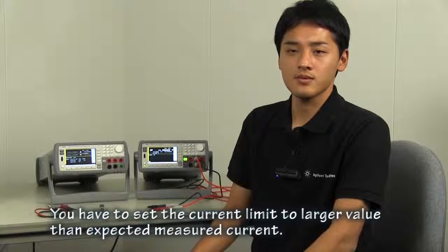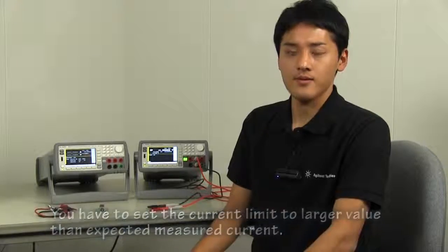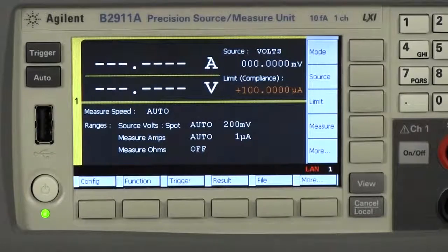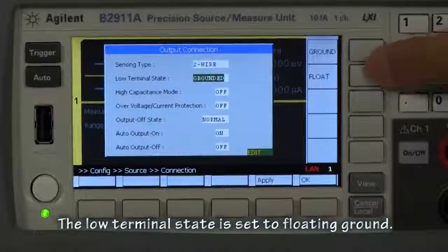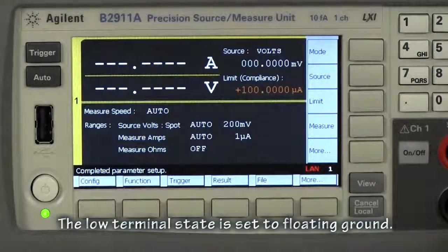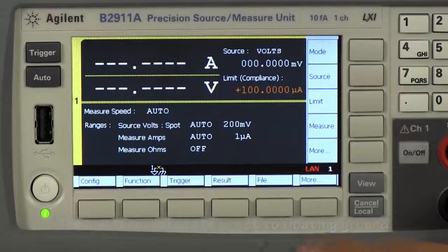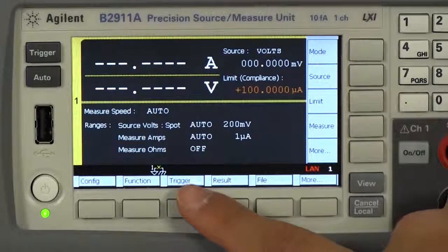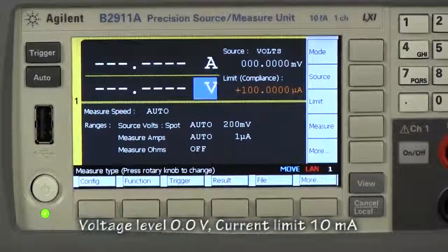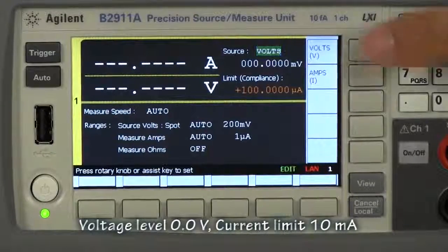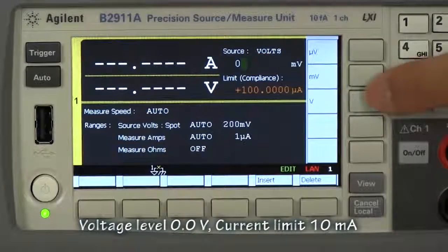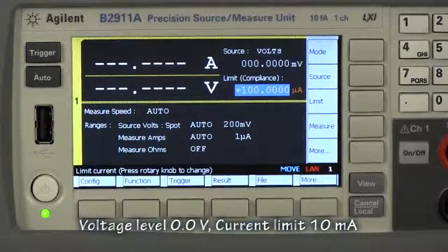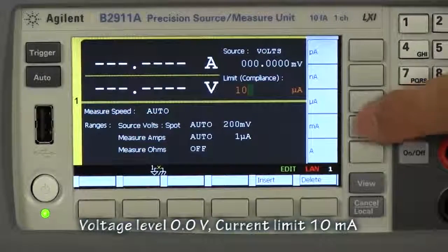I'll show you how to set output conditions with the front panel. I have to set the low terminal state to floating first. This symbol indicates floating state. And then I'll set the source mode to voltage mode, voltage level to 0V, current limit to 10mA.